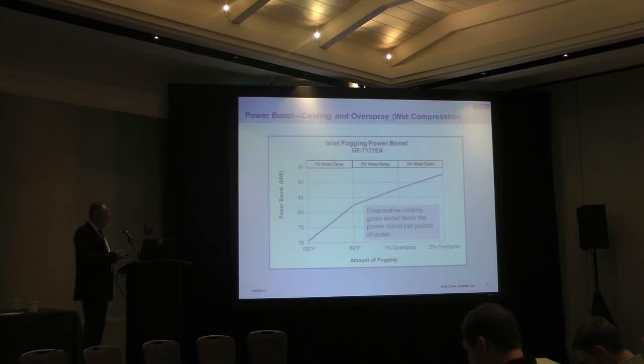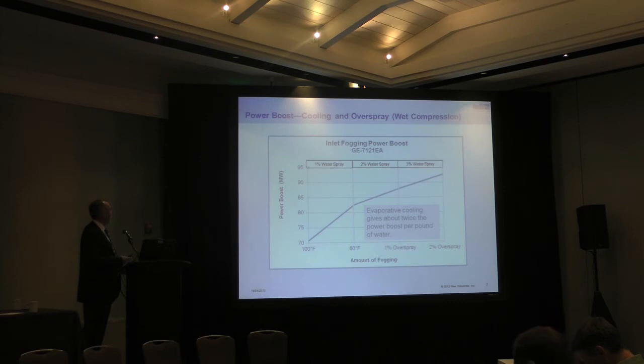And this shows specifically a 7EA turbine, 7121EA, whoops. Not used to this trigger down here. Starting at 100 degrees Fahrenheit and cooling 40 degrees, and I picked that number because that's about 1% of water spray. So to cool from 100 to 60, you had to spray about 1% of the air mass flow as liquid water. In this case, it's evaporating before the compressor, cooling the inlet air, and increasing the output of the gas turbine. The next 1%, for a total of 2% now, becomes overspray. It can't evaporate before the compressor because the air is fully saturated here.